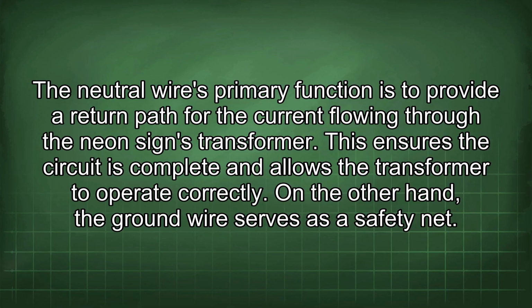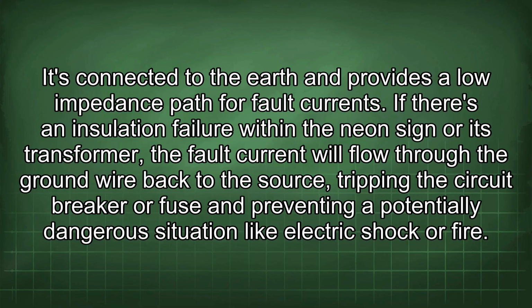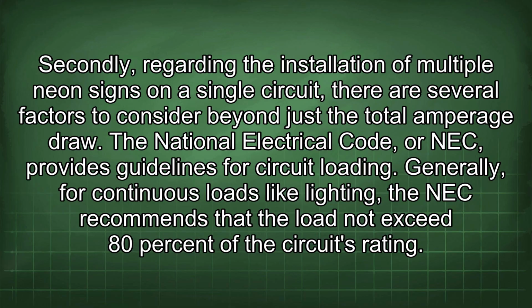On the other hand, the ground wire serves as a safety net. It's connected to the earth and provides a low impedance path for fault currents. If there's an insulation failure within the neon sign or its transformer, the fault current will flow through the ground wire back to the source, tripping the circuit breaker or fuse and preventing a potentially dangerous situation like electric shock or fire.